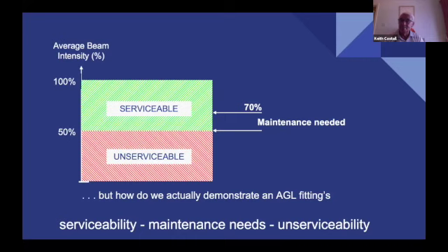And again, within the MARMS system, you can modify that 70% level on all of our reports. Our reports are coded red, green, and blue, where a blue bar for a particular lamp will be between the 50% and whatever maintenance level you've chosen. So if you wanted a maintenance level of, say, 85%, our bar charts will indicate that at whatever specification you have, and then they will draw that in blue to signify that maintenance is required.